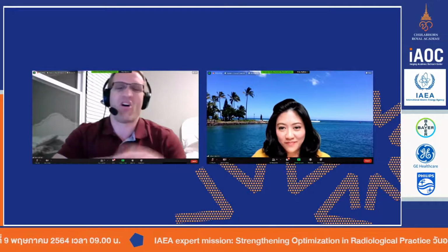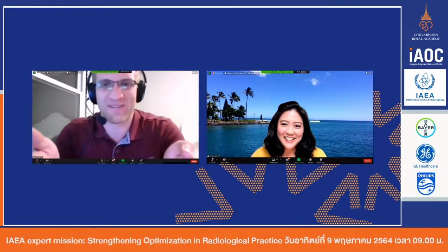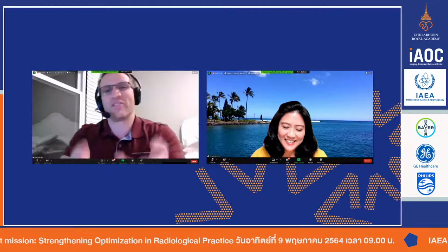And then you start to realize, oh, I'm getting a lot of images in my QI pile. And then you review them the first month or the first quarter, and you realize, oh yeah, all of those were okay. So then maybe you can say, let's move that out a little bit. Let's make that plus or minus 7. And then you start to realize now there's fewer and fewer.